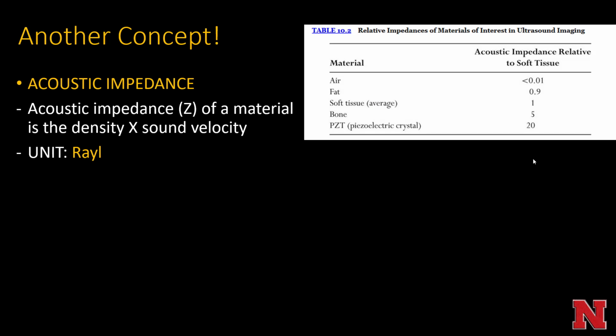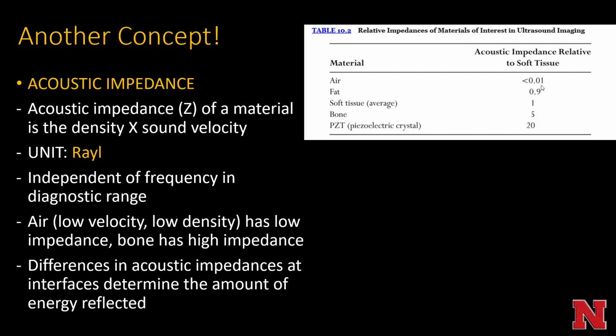Another concept: acoustic impedance, or Z, of a material is the density of the material times the sound velocity, resulting in a unit called the rayl. Here's the relative impedance of different materials. For example, the piezoelectric crystal used by most sonographic transducers to create and receive sound waves has a very high acoustic impedance, as does bone, versus air and fat which have much lower acoustic impedance. This acoustic impedance is independent of the frequency used in the diagnostic range, so it's material dependent, not frequency dependent.